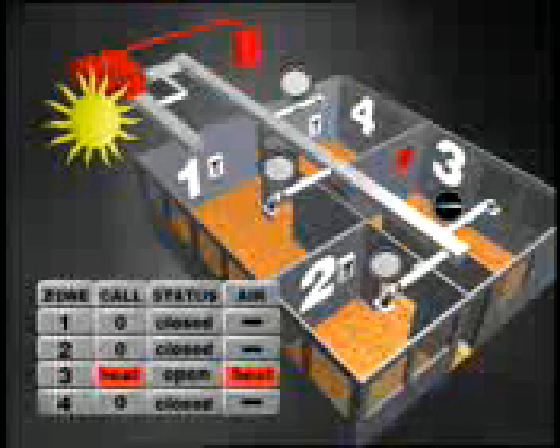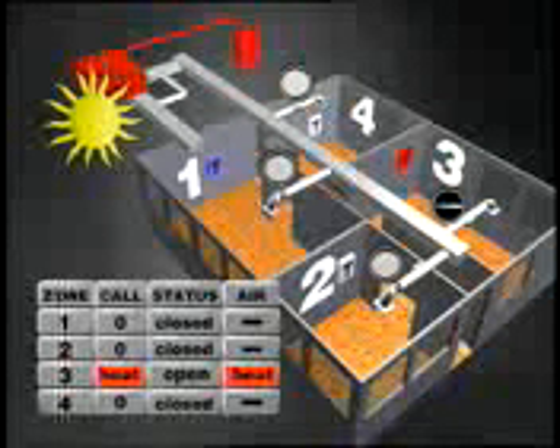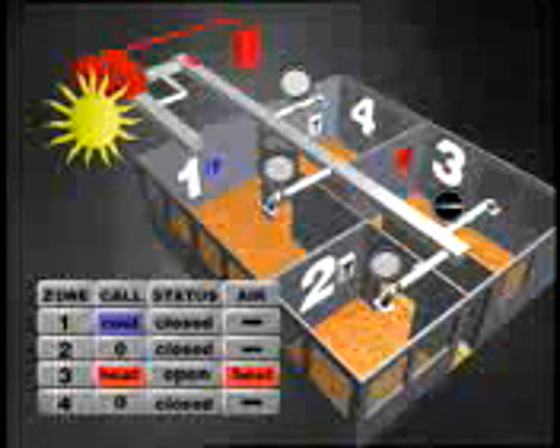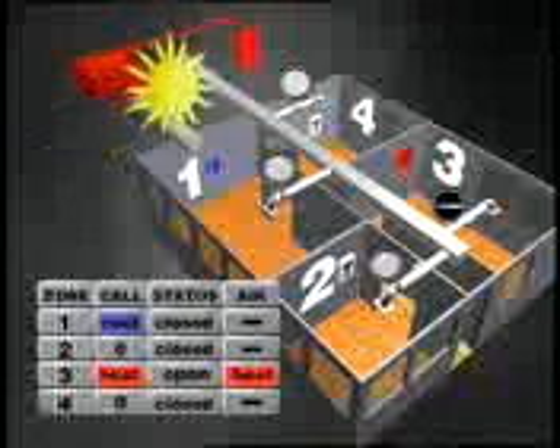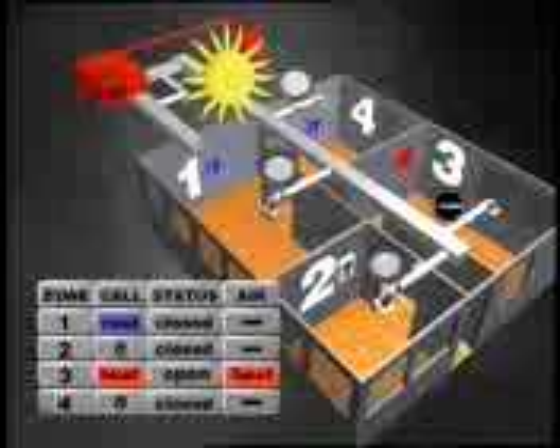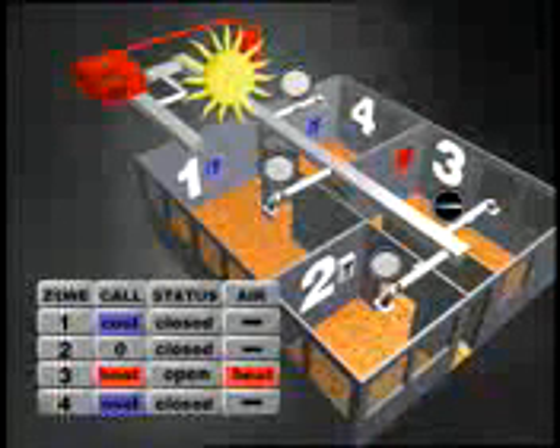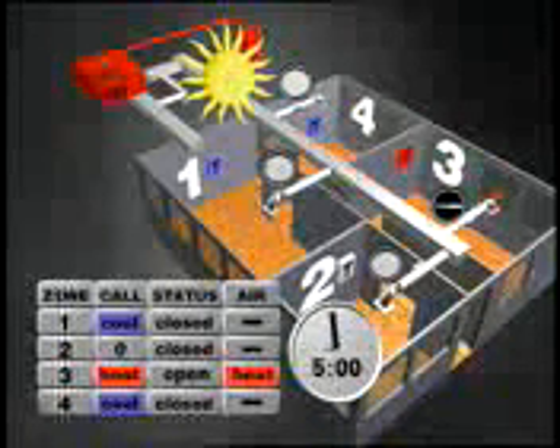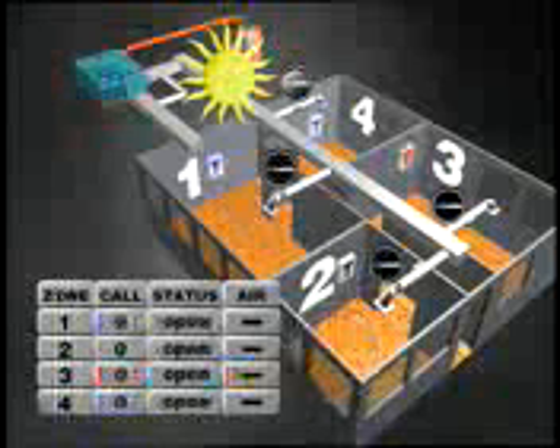System 2000 compensates for peak solar conditions throughout the day. As the sun moves on to Zone 1, it now calls for cooler temperature. However, Zone 3 was first to call, so it remains in the heating mode. With the sun now on both Zones 1 and 4, the controller senses a majority of the system wants cooling. It programs this information, but waits another 5 minutes before taking action, allowing time to satisfy Zone 3. It then shuts down the heating system for 2.5 minutes.